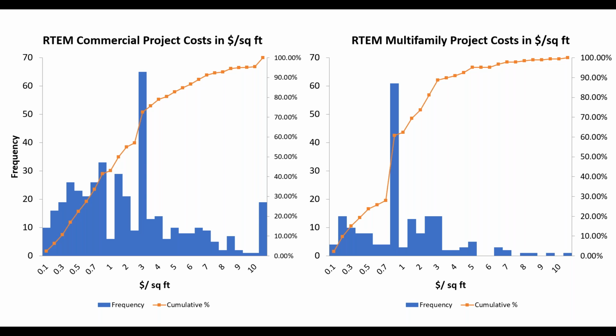If the project already has a BAS and data gateway ready to go, and we're looking at a software overlay, cost can still vary based on how many integrations the customer wants. For example, we ran a pilot set of projects called RTEM Premium, shown in the commercial set farther to the right on the higher cost end, because we required secondary and ancillary systems to be pulled in - lighting, elevators, occupancy and weather information, and monitoring of all utilities in the building versus just electric. Those costs reflect forcing these siloed systems to be integrated, so they came in at a higher price point.